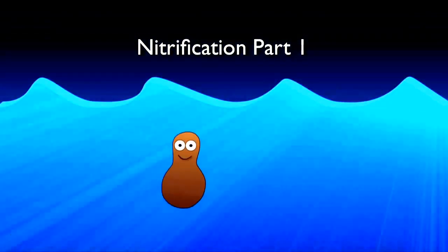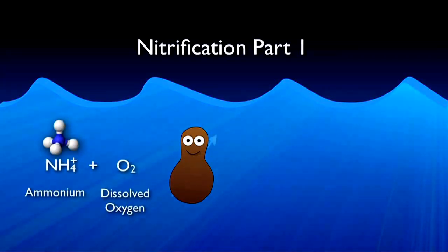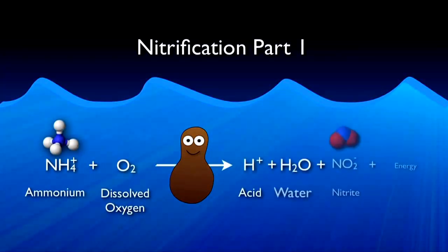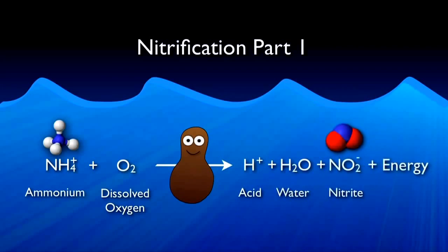Once a healthy population of nitrifiers has developed, the first step — performed largely by ammonia oxidizers — takes ammonium and dissolved oxygen and converts it into acid, water, nitrite, and energy. If the system lacks adequate alkalinity, the acid produced could create inhospitably acidic conditions for the bacteria, resulting in loss of nitrification. The water produced is absorbed in the system and the nitrite moves on to the next step.